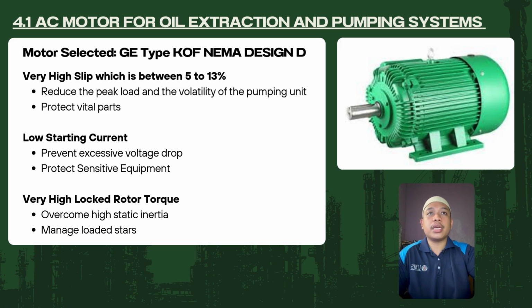Furthermore, it has a low starting current. The operation is in a remote area, so it works on a long distribution line, which can cause a quick surge and result in huge voltage loss. So it requires a low starting current motor to prevent excessive voltage drop. Moreover, it can protect the sensitive equipment. If we choose high starting current, it can cause motor windings to generate a large amount of heat in a short time, which causes a sharp rise in winding temperature.